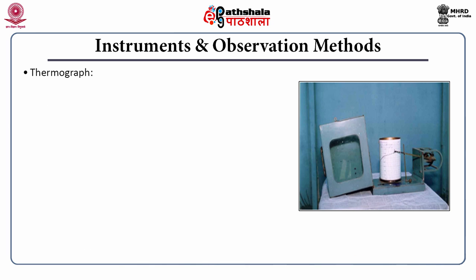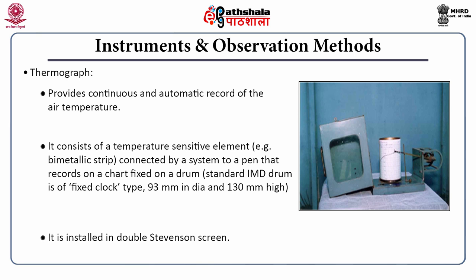The thermograph provides a continuous and automatic record of air temperature. It is placed inside the double louvered Stevenson screen. The thermograph has a temperature-sensitive element — generally a bimetallic strip is used as a sensor — connected by a system of levers to a pen. That pen records on a chart fixed on a drum. The standard IMD drum is a clockwork type with a diameter of 93 millimeters and 130 millimeters in height.